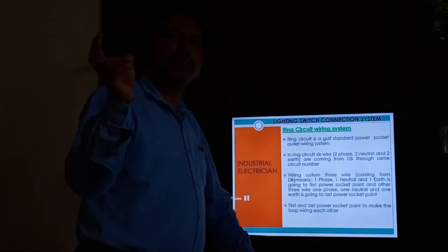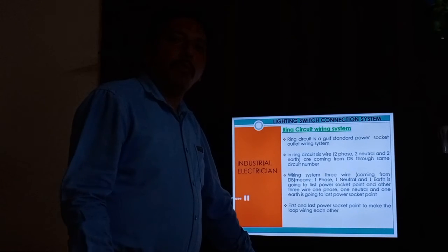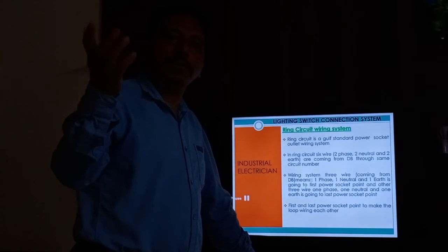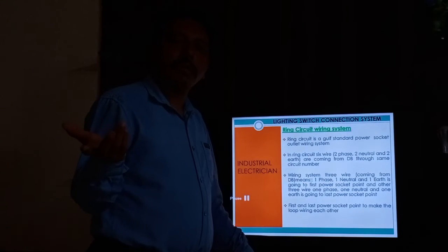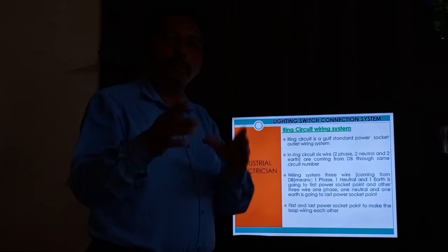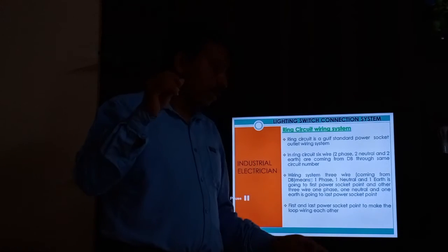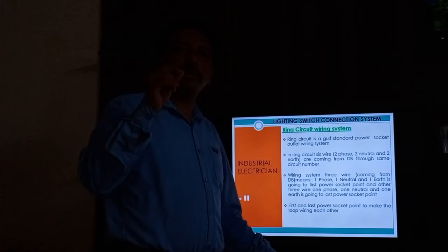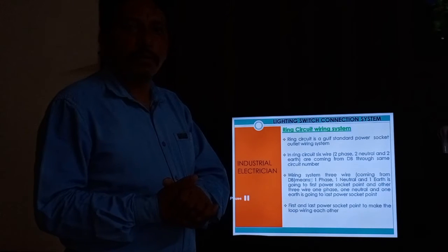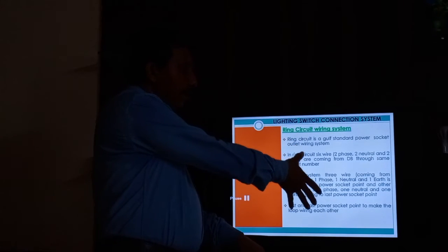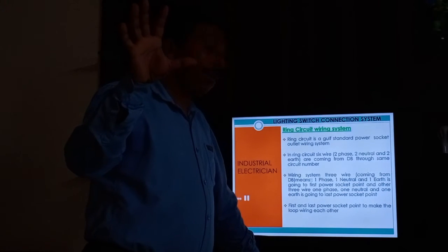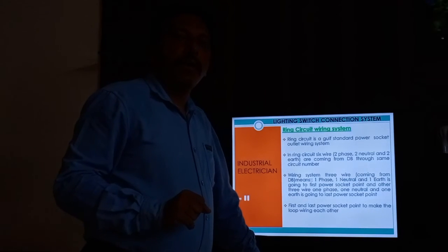Water heater we can use ELCB, because a water heater can be fitted inside the bathroom or inside the kitchen. If there is a chance of water leakage, any shock is a hazard. ELCB has a 30 milliamp trip, so we use ELCB in this kind of wiring.